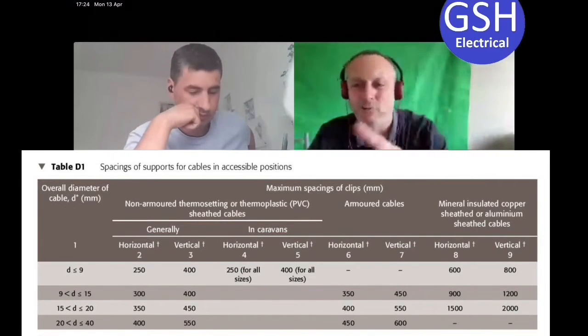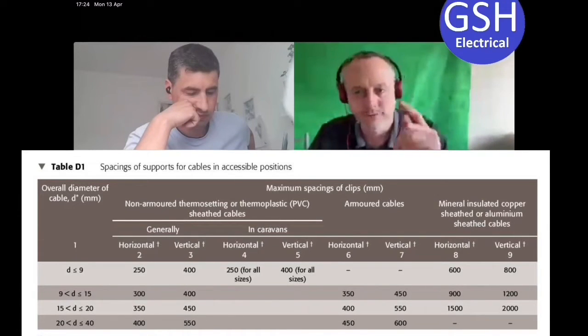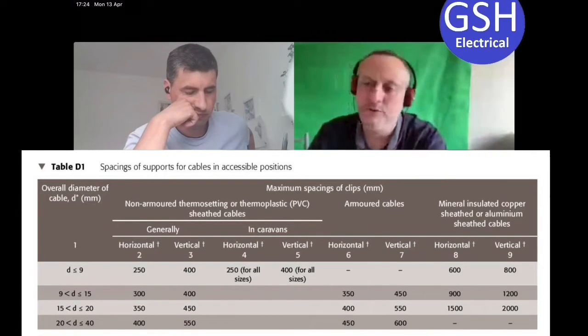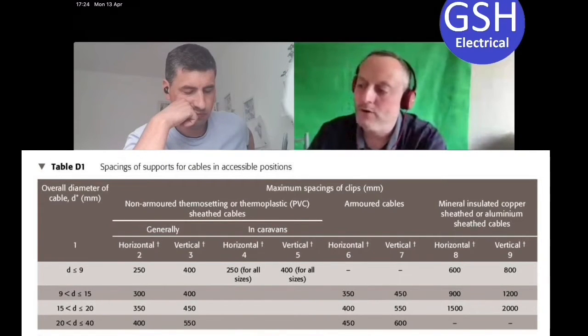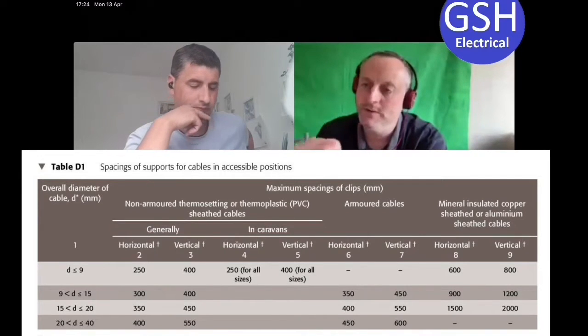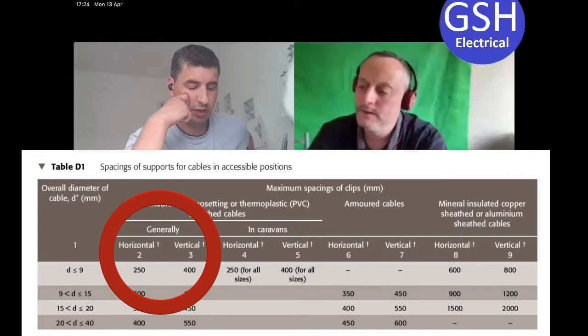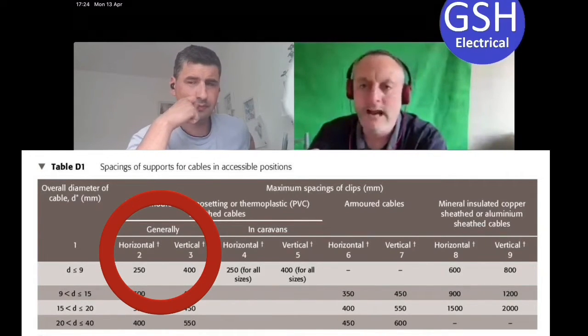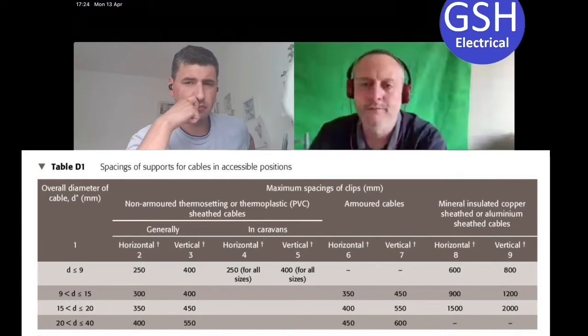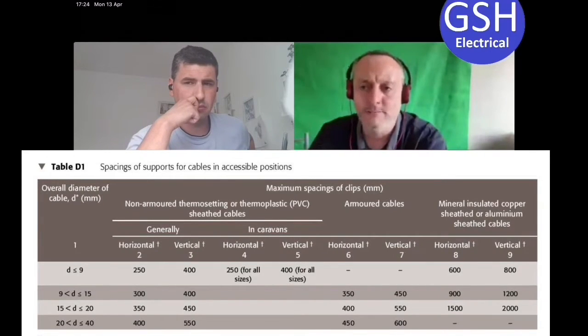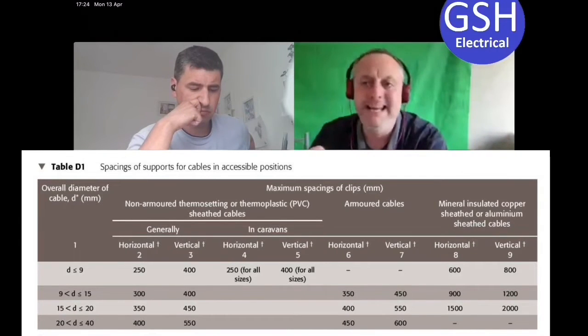That first row covers diameters up to and including nine mil. We have a choice about caravan or general use, but we're in a domestic dwelling so we're using columns two and three. The maximum horizontal distance is 250mm and vertical is 400mm. These are maximums - you can clip more frequently if you want, you just can't be less frequent.